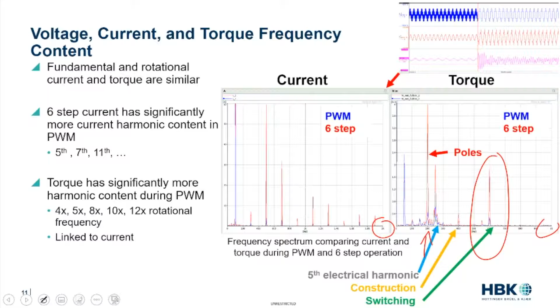We not only have an input from how we modulate the voltage or current, but also influences by the torque loading on the frequency spectra. In this measurement you see a different machine than before, with 3 loads: one at no load at all, one at 30 Newton meters, and one at 26 Newton meters of torque. Then we can see that the inverter signature shows a strong torque dependency, but not only torque.